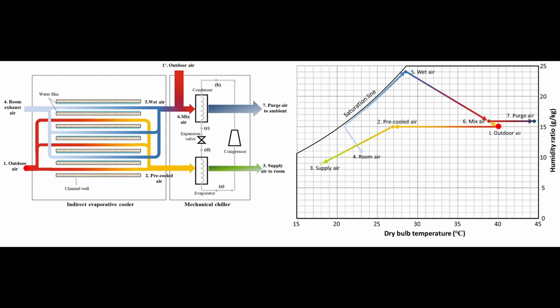Now we will look at the outdoor air until room supply. At the starting point, the outdoor air will pass through the channel wall, where the dry bulb temperature decreases while maintaining its humidity ratio. After it has passed through the channel wall, it will become pre-cooled air. The pre-cooled air will then go into an evaporator, where its dry bulb temperature and humidity ratio decrease until this point here, where it will be supplied to the room.